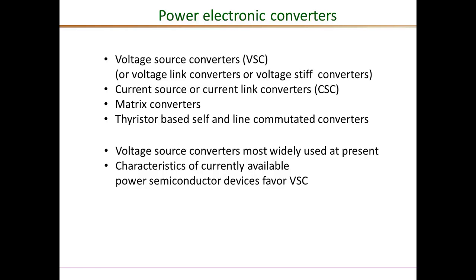The reason for that is the characteristics of currently available power semiconductor devices like MOSFETs and IGBTs. They have characteristics that are well suited for voltage source converter requirements. For example, current source converters need bipolar voltage blocking capabilities, which is hard to achieve in a single device. Therefore, voltage source converters are mostly used, and that is why the focus of this module is going to be completely on voltage source converters.